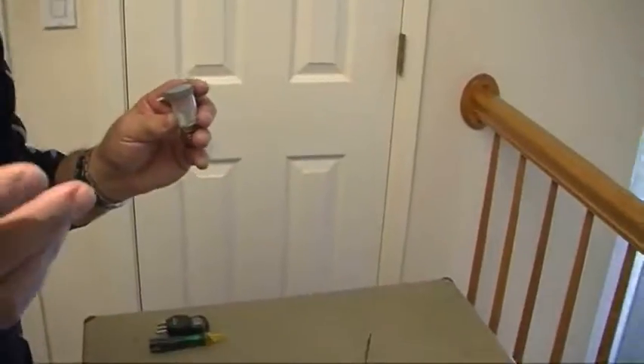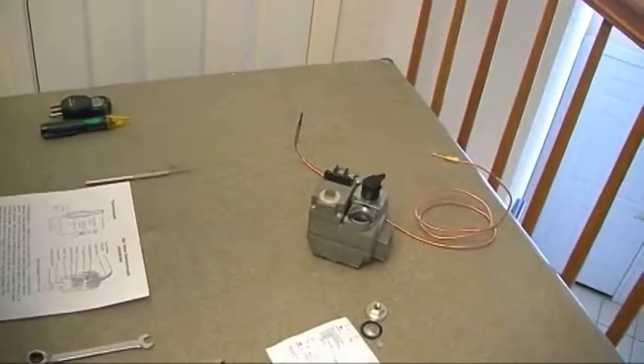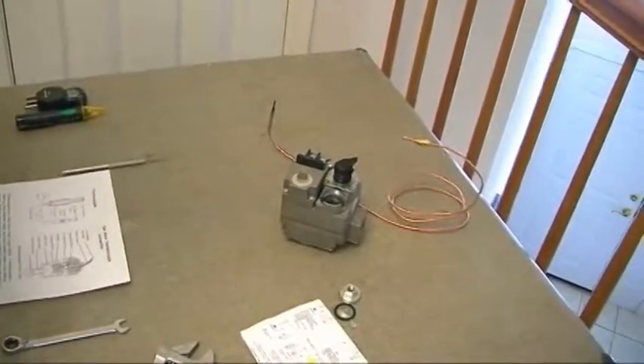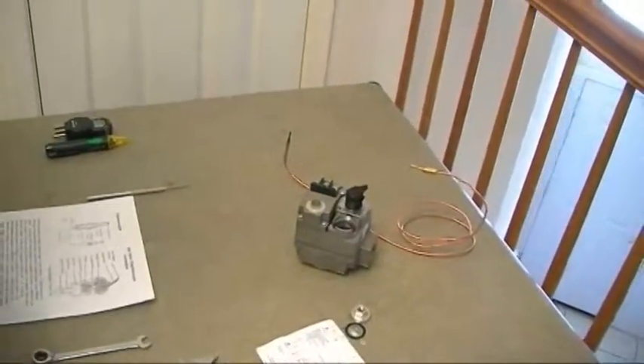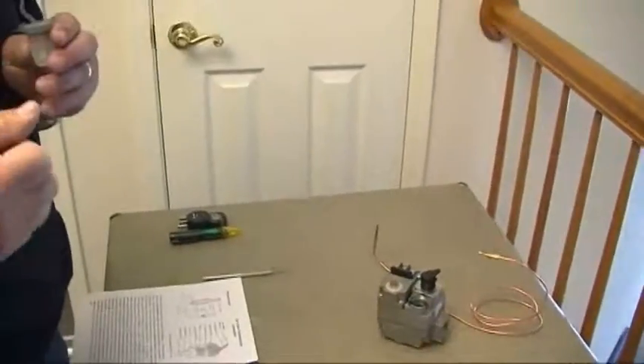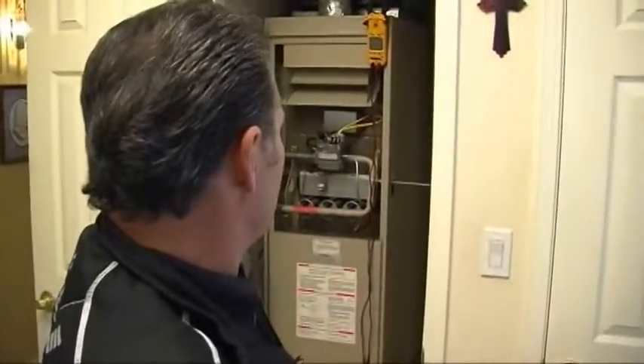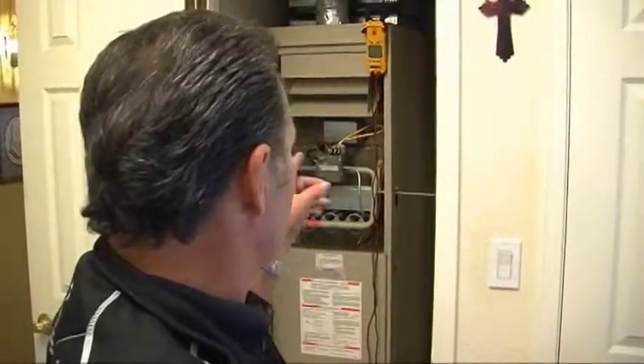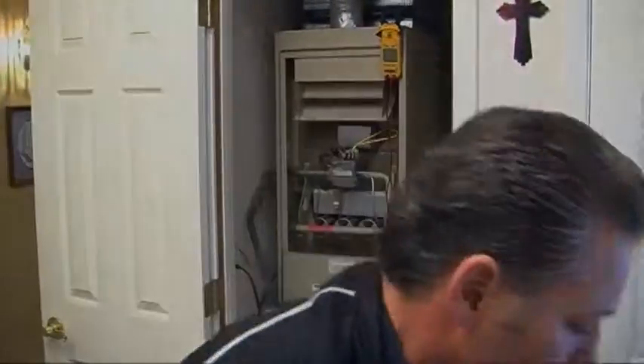The pilot stays lit as long as it's producing a minimum of 20 millivolts. I mean, you can go down to 17, but if you're down below 20 millivolts, you need to either clean or replace your thermocouple. So earlier today, we changed the gas valve on this Lennox unit, and we're going to do a live millivolt check on our thermocouple. Okay? See you in a moment.